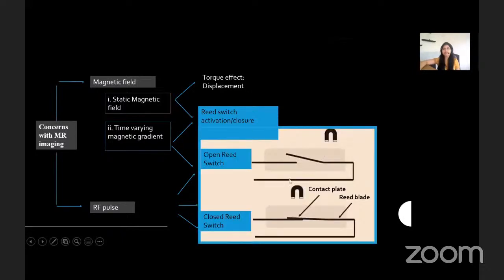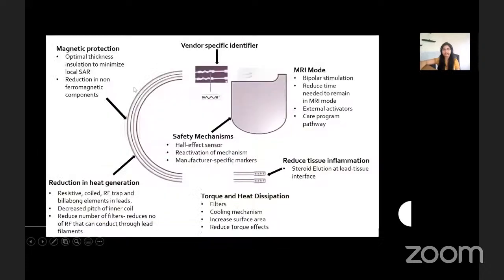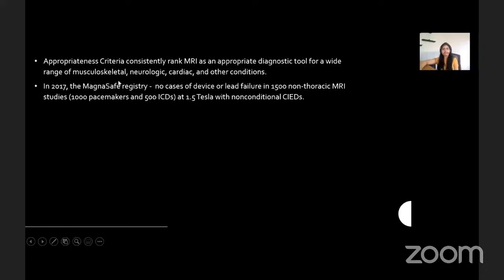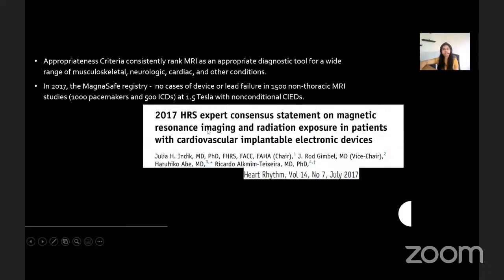Time-varying magnetic gradients can lead to reed switch activation. Recent developments in device engineering have led to devices whose operation is largely resilient to electromagnetic interference in the MRI environment, particularly at 1.5 Tesla. These advancements include reduction in the amount of ferromagnetic material, general robustness to electromagnetic interference, improvement in circuitry sensing and detection algorithms. For example, the reed switch is replaced by a Hall sensor with more predictable behavior. With these developments and studies such as the MagnaSafe Registry demonstrating safety related to non-MR conditional devices, a comprehensive consensus report has been developed detailing recommendations for CT and MRI in patients with CIEDs, endorsed by several cardiologic and radiologic American societies.